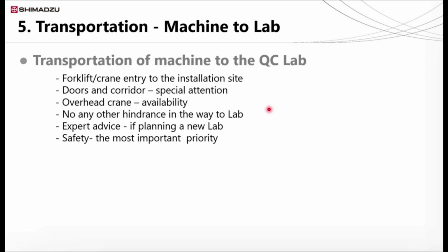Forklift and crane entry. UTM machines are heavy, especially hydraulic machines, which may weigh many tons. So as you can imagine, a forklift is needed to handle the machine. Make sure that there is enough space for the forklift to reach the installation site without any hindrance. Pay special attention to doors and corridors. Measure the door size in advance and make sure the forklift will pass through the door smoothly. If overhead cranes are available, you can make use of them, no problem, but make sure overhead cranes are tested and certified.